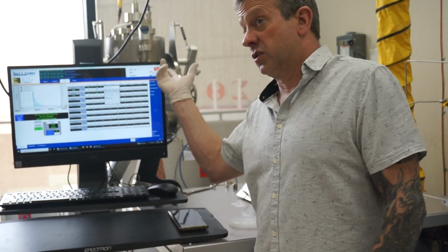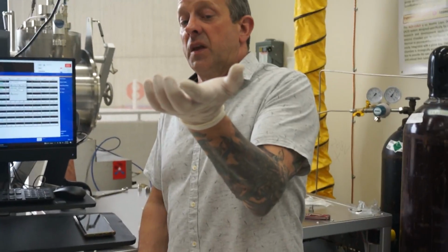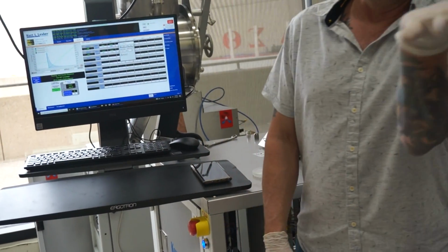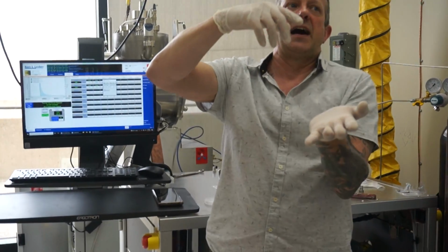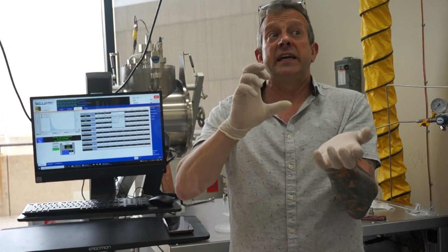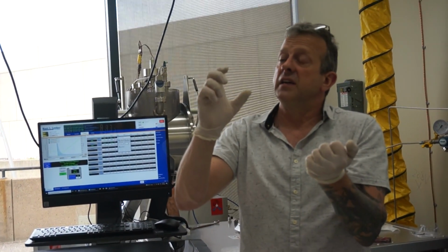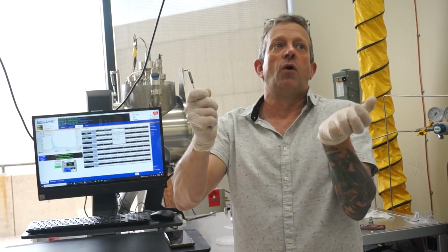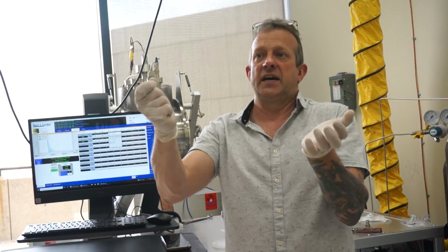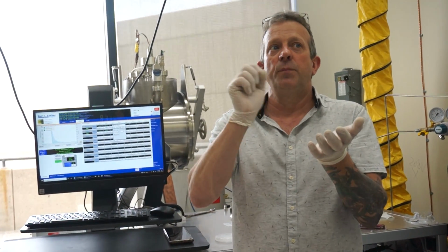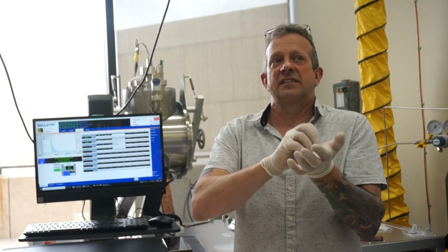Physical vapor deposition, in regards to this, you have a target. You have RF on there too, or just DC? That's RF and DC. You have two guns in here, at least two. So you have a target, and you have a difference of potential. Then you have a gas. The gas lights the plasma. That creates ions, ionized. Now it's charged. So you have a negative pole and you charge the ion, and what that does is it bombards the target. You release little bits of particles, and that's the sputtering part of it.